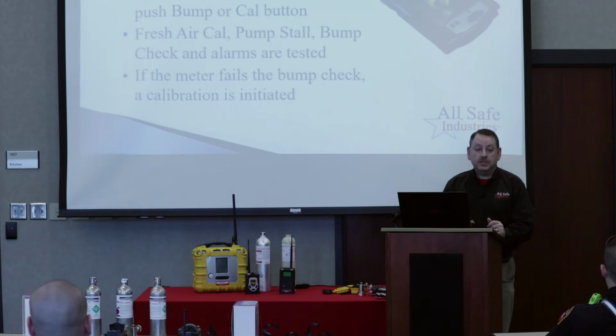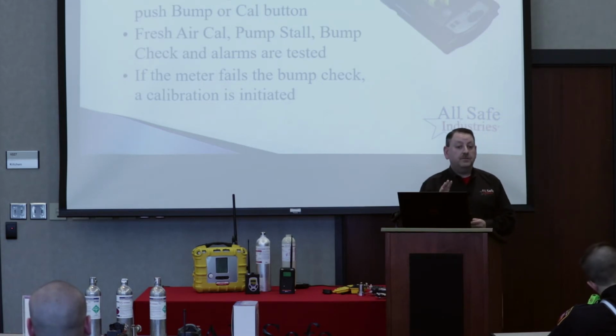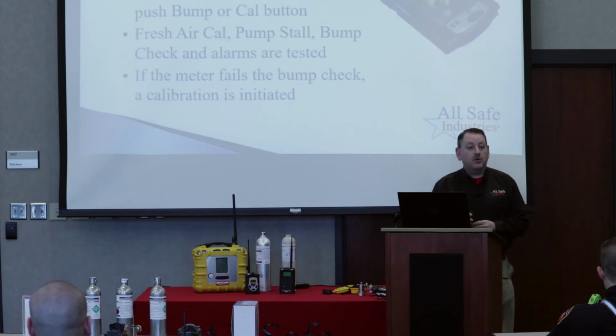Now let's talk about using the instrument. So the first thing I want to start off with before you turn the meters on is that if you're going to run your bump check before each day's use using the cradle, you'll keep the meter turned off and you'll put the meter in the cradle while it's off. As soon as you close that hood down, the cradle recognizes that you've engaged an instrument, and the cradle turns the meter on in calibration mode so that it's ready to go. So remember, if you're going to use the cradle to do your initial test for the day, start with it off, cradle it, close the hood, and then after the cradle warms up, you'll just pick bump or cal to calibrate the meter. Okay?